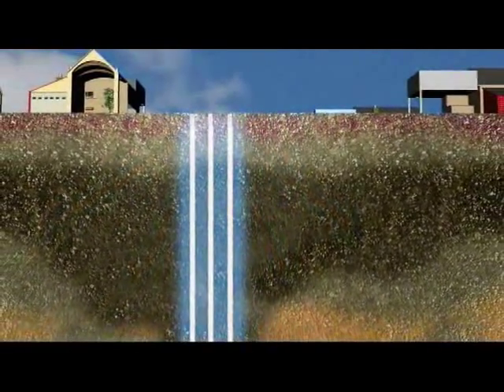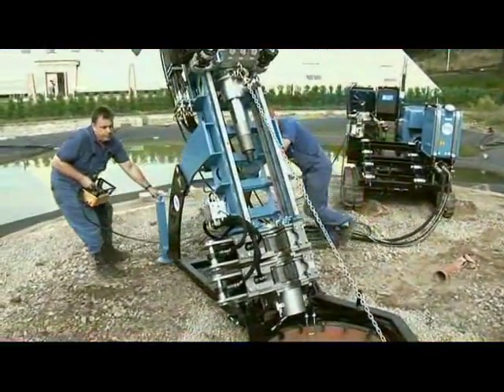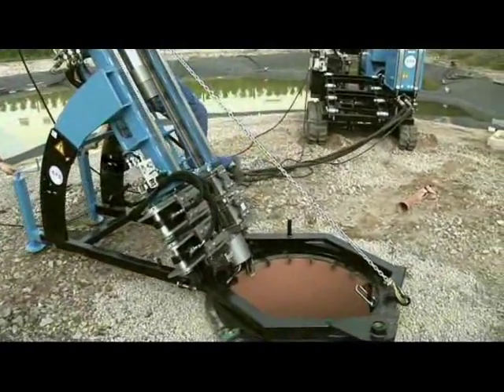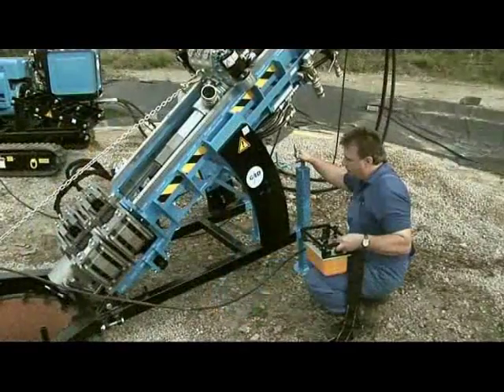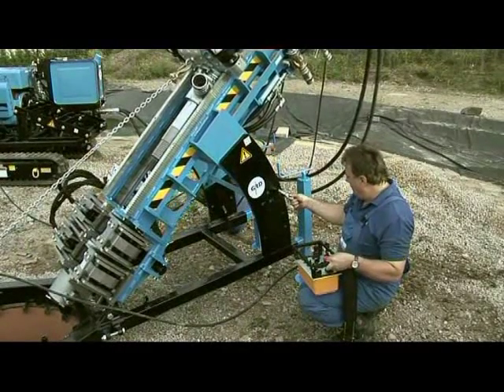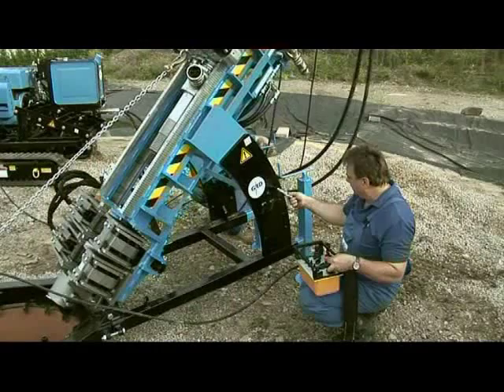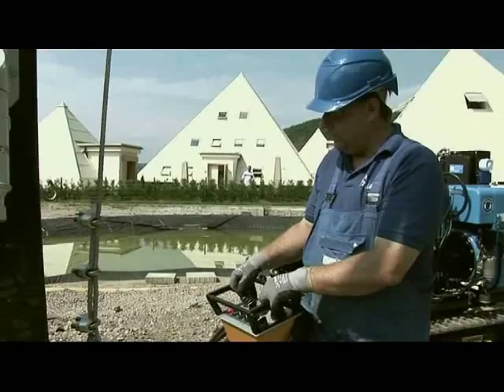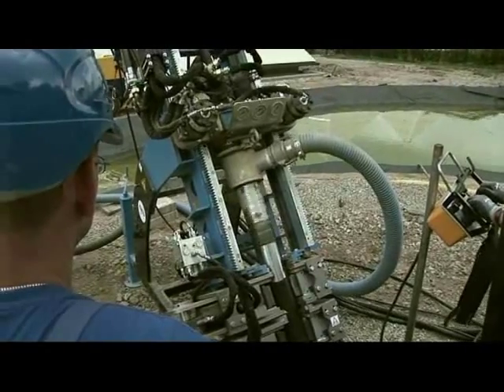Due to the radial heat pipe arrangement, the mutual influence is lower than with vertical heat pipes, and the thermal gradient is high. To start the next bore, the bore rig is simply repositioned manually above the rotary ring. The GRD system allows for bores with an inclination angle between 35 to 65 degrees — the larger the spread, the lower the mutual influence. Once more, the GeoDrill 4R bore rig has proved its flexibility and efficiency.